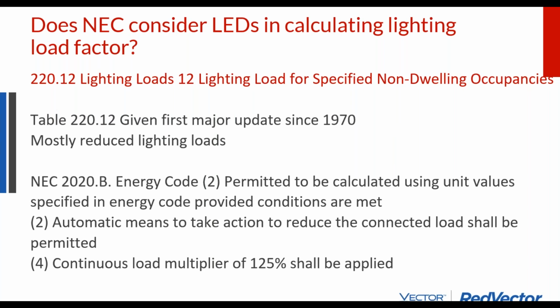And so the lighting loads have been substantially reduced for NEC 2020. And then here's another one. It says you can calculate units provided certain conditions are met. Automatic means to take action and reduce the connected loads shall be permitted. If you're calculating a continuous load with your engineering calculation, you still add an additional 25% to that.